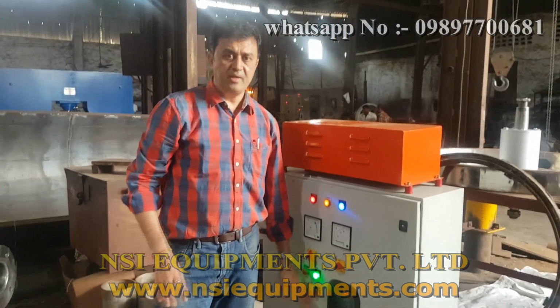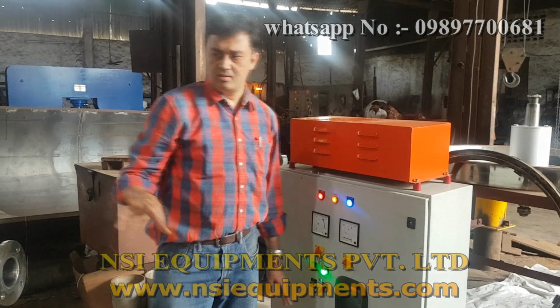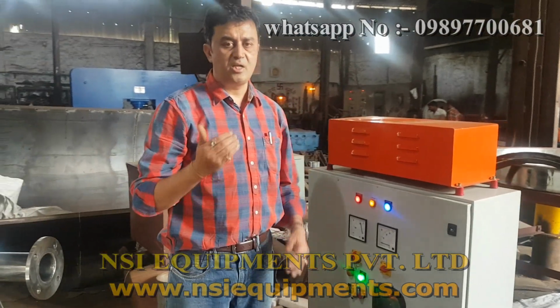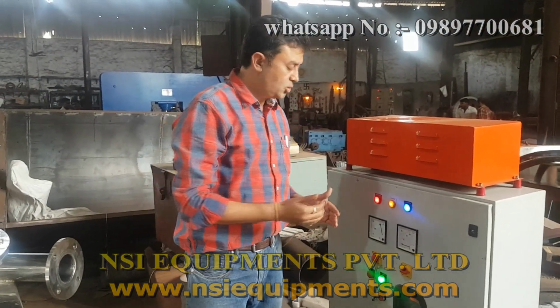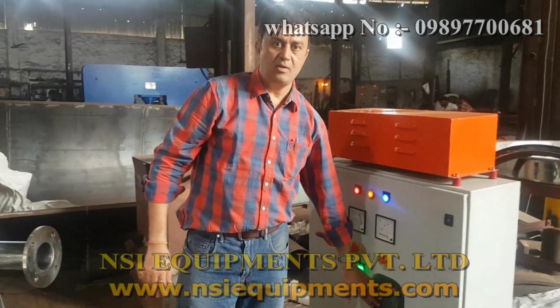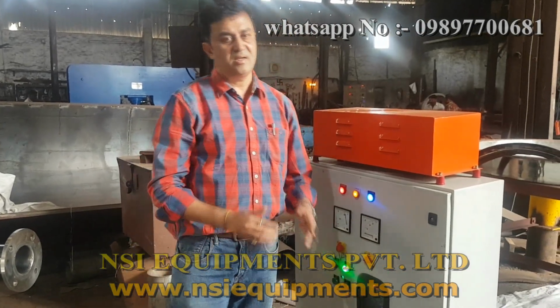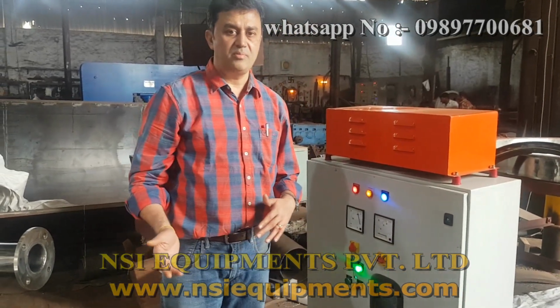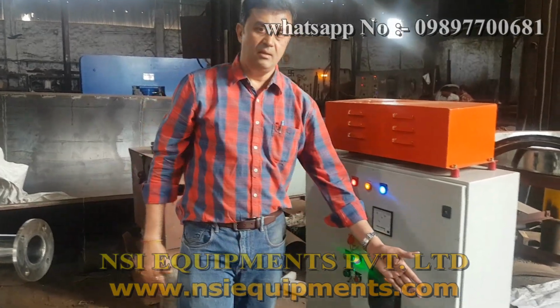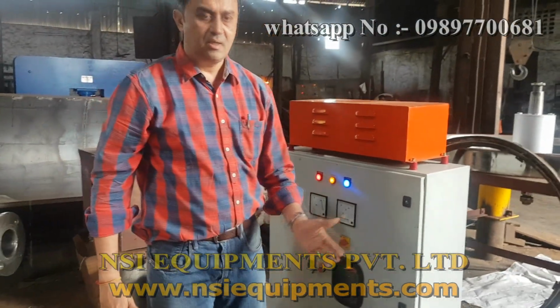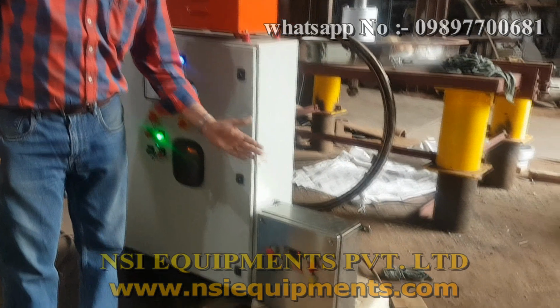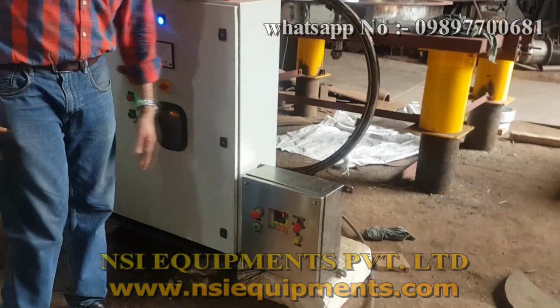The VFD even takes up the soft start of the centrifuge because the initial torque is high. So to take up the torque, the VFD also assists in that. Plus it does the reverse current braking of the machine also. Plus we get different variable speeds. If we want to set speed 1, 2, 3, that also we get in this centrifuge.